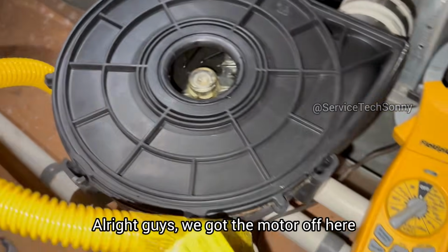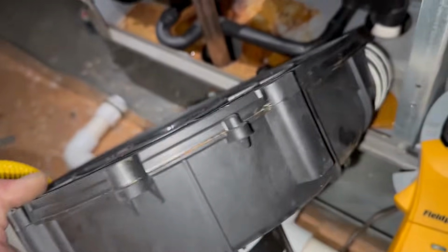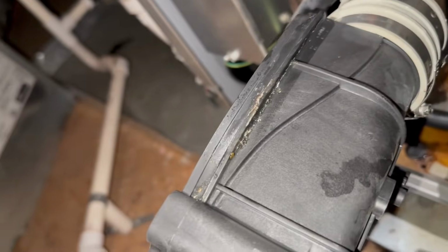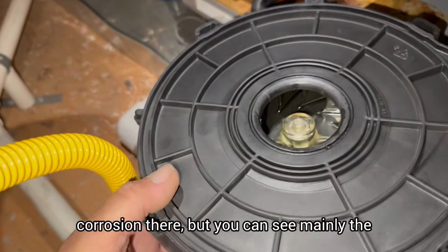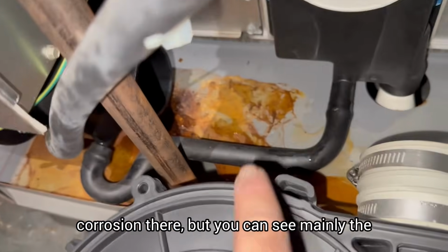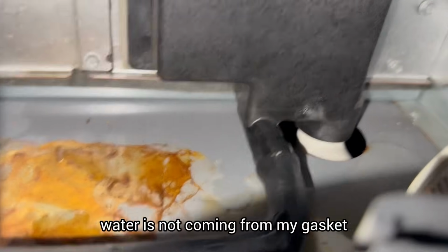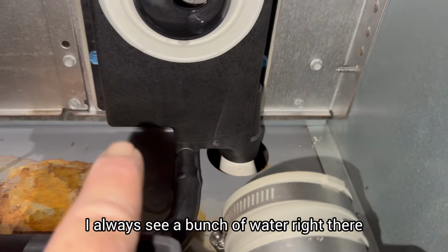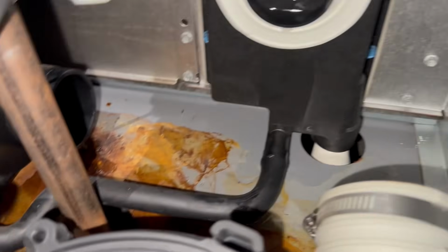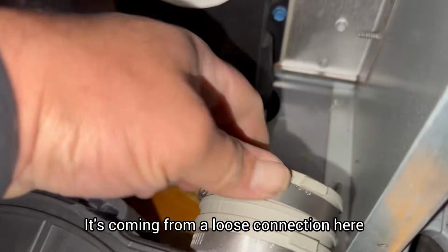All right, guys, we got the motor off here. Got a little bit of corrosion there, but you can see mainly the water is not coming from my gasket. I always see a bunch of water right there. The gasket's all ruined, but it's coming from a loose connection here.